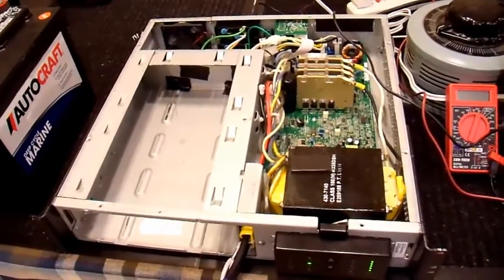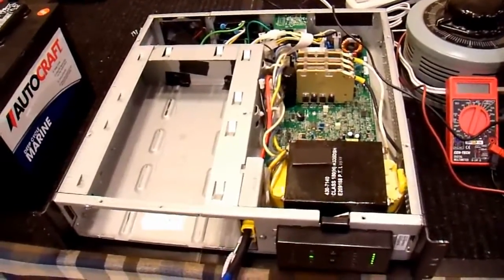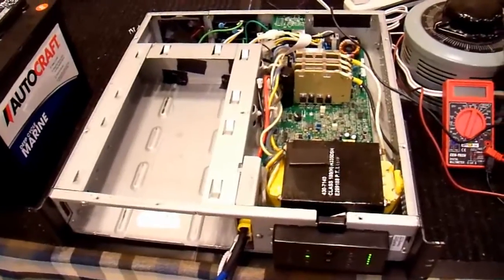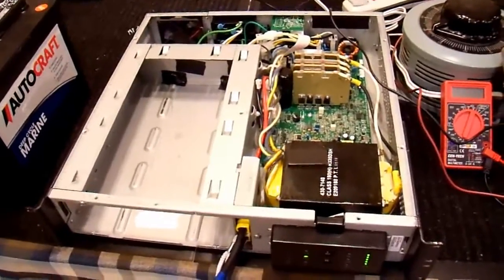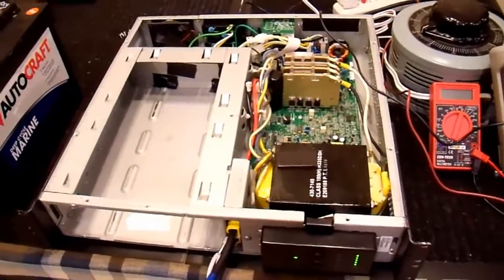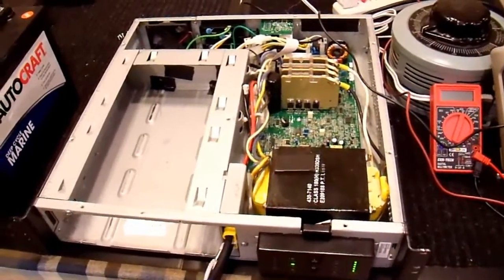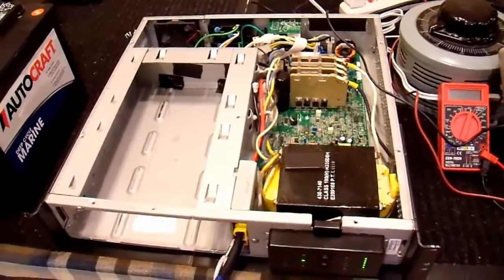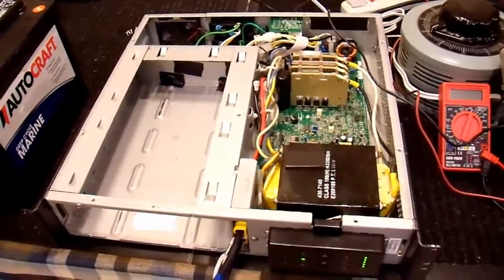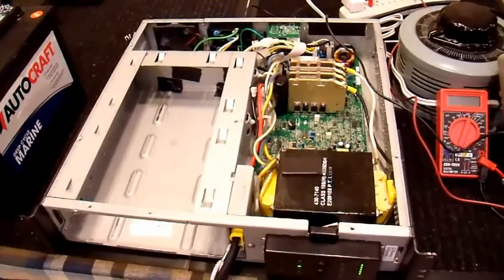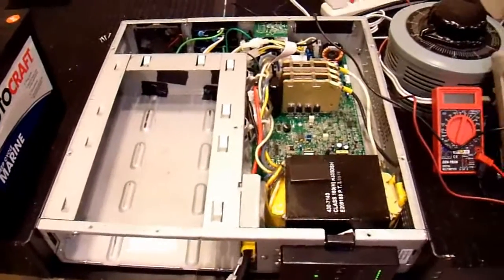So basically, if you have a load that is being powered off of the wall or UPS and it switches between UPS power and wall power, either from wall power to UPS power or from UPS back to wall power, either way, you would get a discontinuity in that output voltage waveform if they were not perfectly synchronized.